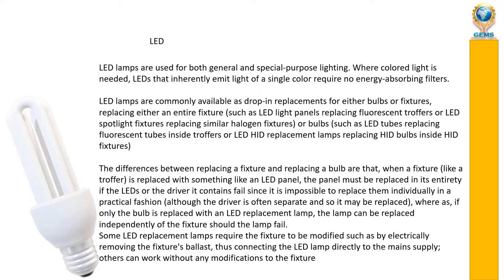LED lamps are commonly available as drop-in replacements for either bulbs or fixtures. LED light panels can replace fluorescent bulbs inside fixtures. When a fixture is replaced with something like an LED panel, the entire panel must be replaced if the LEDs or driver fail, since it is impossible to replace them individually.